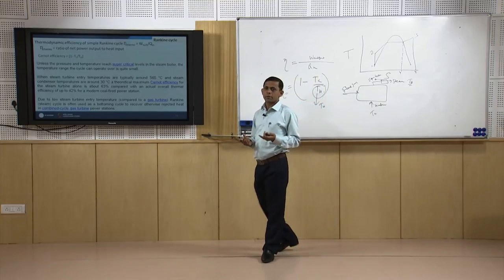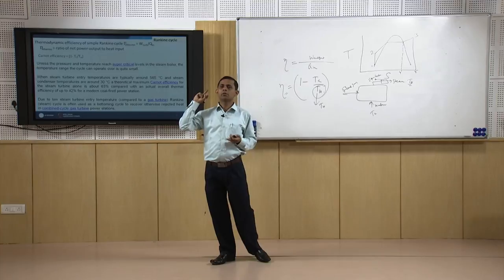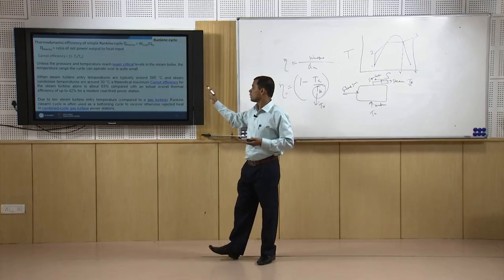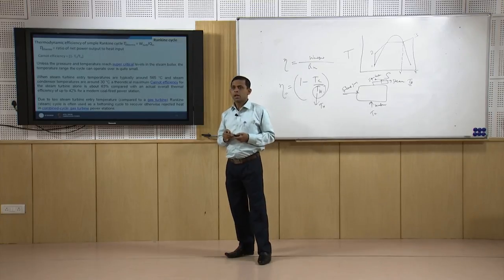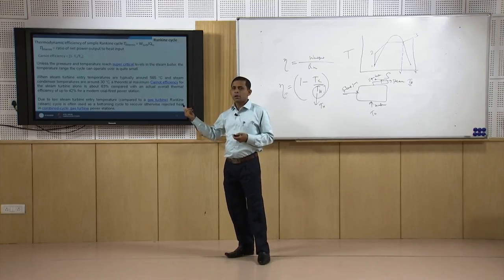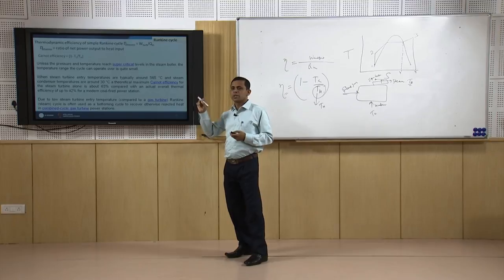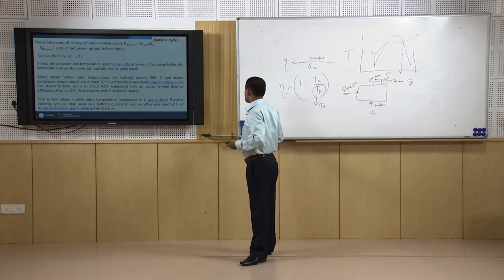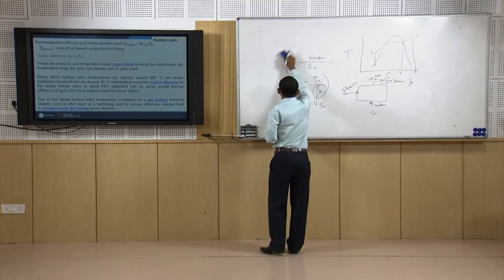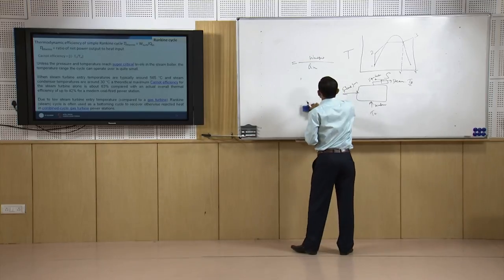So due to low steam turbine temperature, with respect to gas turbine, the gas turbine temperature is around 1500 degree centigrade, but here it is around, say, in supercritical condition, 565 degree centigrade. So due to this low temperature requirement for steam turbine, this is used in the bottoming cycle of a combined cycle plant.